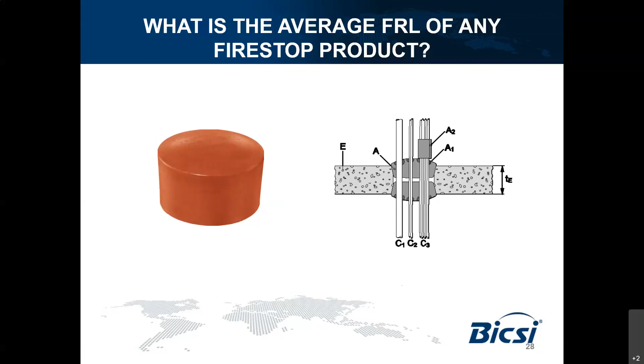The typical answer is people will say, I know this is a 2-hour material, or a 4-hour, 240-rated material. However, the reality is there's no rating for the material itself. No individual firestop product from any manufacturer carries a fire rating. Only an entire firestop system is rated.